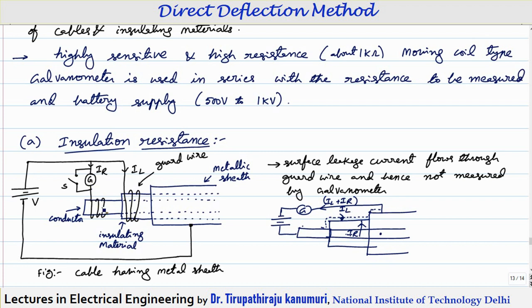That is the basic principle. We provide the guard ring connection so that only the current passing from the conductor to the sheath is measured. Whichever current is leaking through the surface — that leakage current is bypassed through the guard ring, passes through the surface over the metal sheath, and will not be measured by the galvanometer. Through the galvanometer, only the current passing from the conductor through the insulation is measured. That is why the guard ring is used in practice.